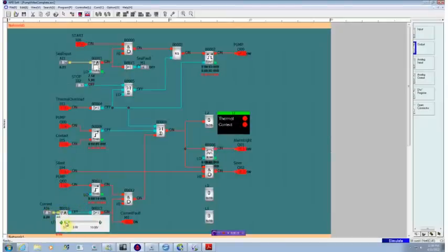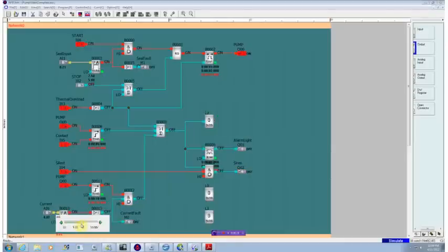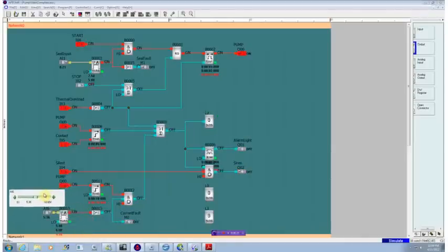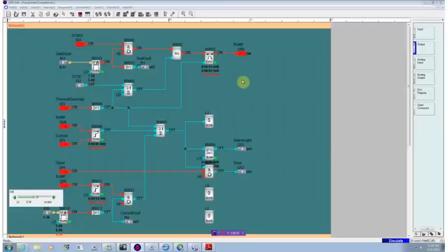So if we bring this up to a valid range between five and six, we now have current flowing through the motor. The alarm condition is being satisfied. The pump is on and things are running quite nicely.